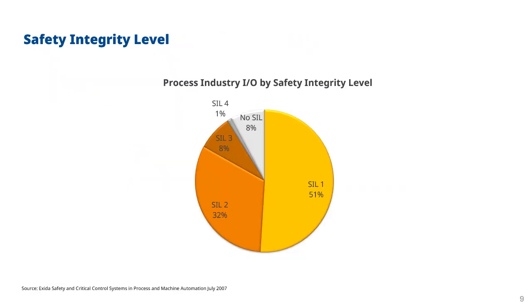So here's an analysis of safety integrity levels in the process industry. Generally, we find that about 51% of applications are SIL 1, so that's by far the majority of them. About 32% are SIL 2, 8% are SIL 3, only about 1% are SIL 4, and then there's also some applications where no SIL is required, where there's no safety. So if there's no SIL, you could use any application. A standard PLC system would be fine.